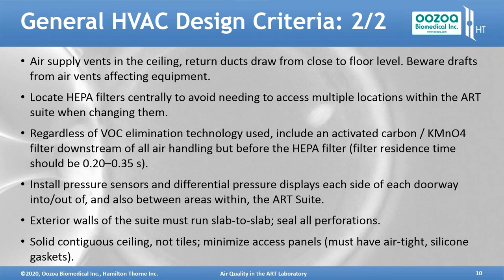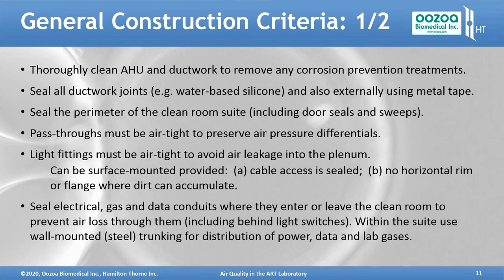In terms of general construction criteria, thoroughly clean the AHU and all the ductwork to remove corrosion prevention treatments before installation. Seal all the ductwork joints, for example, using water-based silicone, and also seal them externally using metal tape around the outside. You'll see this metal tape, silver shiny stuff, on all the HVAC ducts.